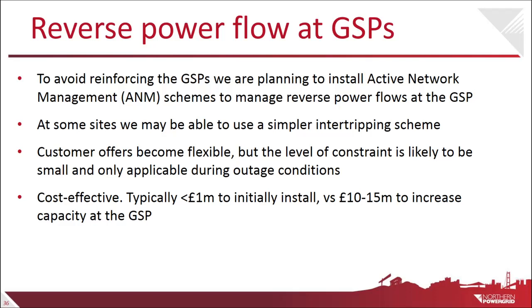So the solution that we're moving towards there is to install an active network management system, which we gave a webinar about a month ago, which tells you a little bit more about how we apply active network management. But generally speaking, it costs about £1 million to initially install. The incremental cost of adding customers to that scheme is significantly less than that, and that's compared to a typical cost of £10 to £15 million to add more transformer capacity at the GSP. So it's a relatively cheap way to solve the problem. And it's also addressing a situation that doesn't occur very often, so the likelihood of constraint for the end customer is relatively small.